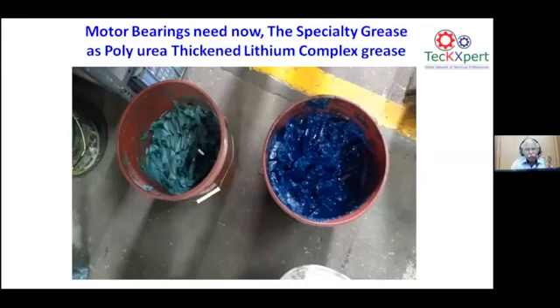Once you are doing it for a multi-purpose grease once in 3 months or 6 months, this can be done even once in a year or once in a year and above as well. And definitely the penetration strength of this grease is more, and it will maintain heat dissipation excellently. It will remove the heat from the motor.